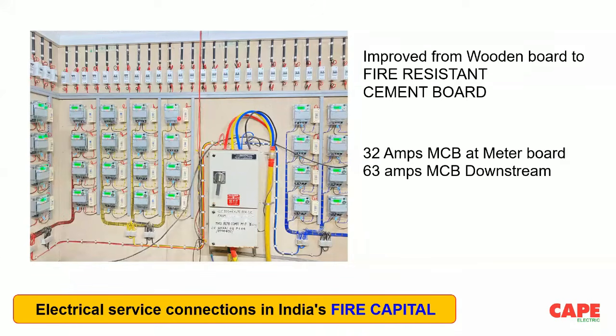Say, for example, near the meter, there is a 32 amp single pole MCB, and at the top, these are double pole MCBs provided by the builder, and these are 63 amp MCBs. So the incoming is 32 and the outgoing is 63. Of course, the wire is not sized enough to carry this much current.